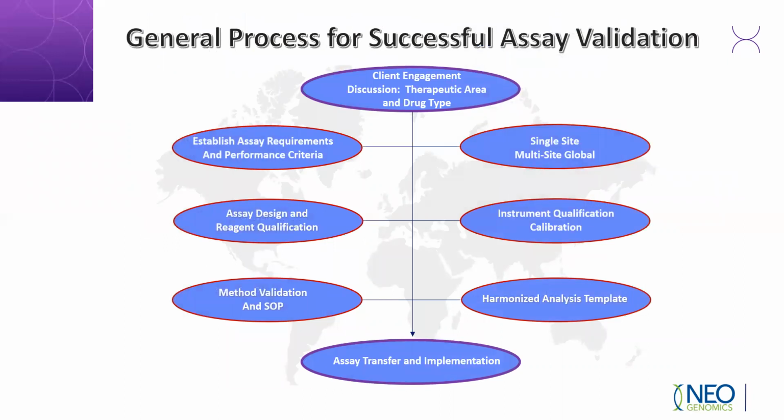So in order to build a process for successful assay development, there are some aspects that should be implemented. First, we must establish the assay requirements themselves. This is achieved through sponsor and provider interaction and communication. Cannot stress this point enough, as it is very key to do it right from the very beginning. You don't want to be midway through the validation only to get very pertinent information later and have to start over or even do a full redesign. This includes determination if the method is needed at multiple sites as well. Knowing this from the beginning minimizes the caveats that could cause snags in the process. This loses the one commodity that you can't ever get back, and that's time.